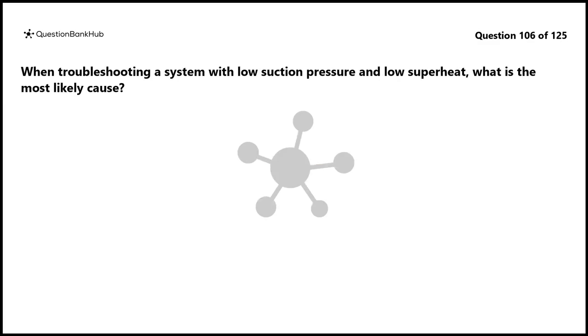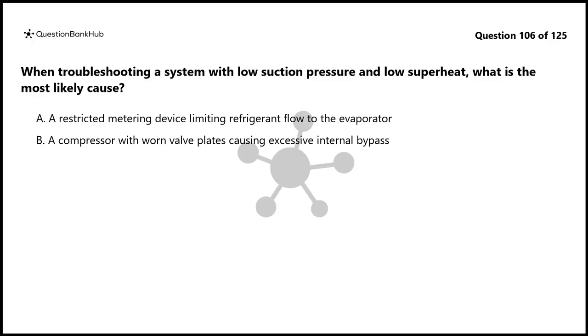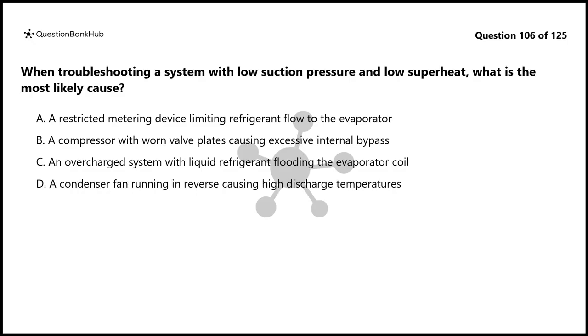Question 106. When troubleshooting a system with low suction pressure and low superheat, what is the most likely cause? A. A restricted metering device limiting refrigerant flow to the evaporator. B. A compressor with worn valve plates causing excessive internal bypass. C. An overcharged system with liquid refrigerant flooding the evaporator coil. D. A condenser fan running in reverse causing high discharge temperatures.